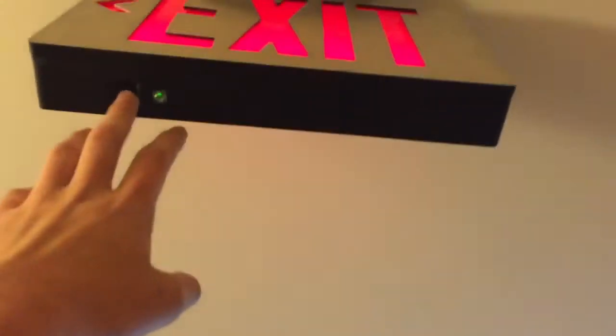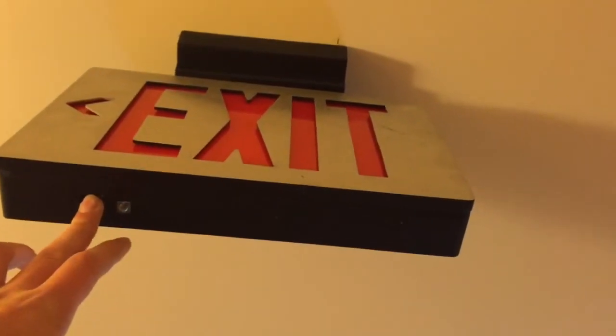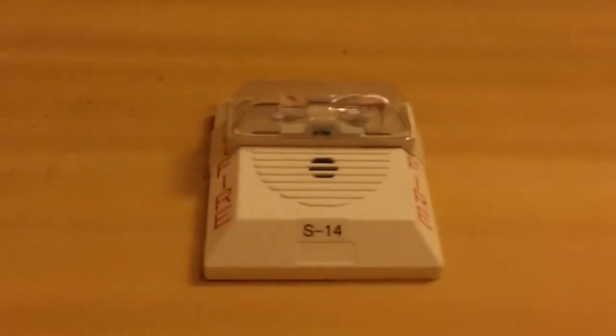NS. Here's another Signature Series sign. It doesn't work. And it's pointing at a door. This is a guest room. Doesn't make sense. Here's the hotel. Or, not hotel, elevator room for your elevator fans. Two detectors right beside each other. TrueAlarms. Sprinkler, very dusty. NS. Better hurry, here comes someone.